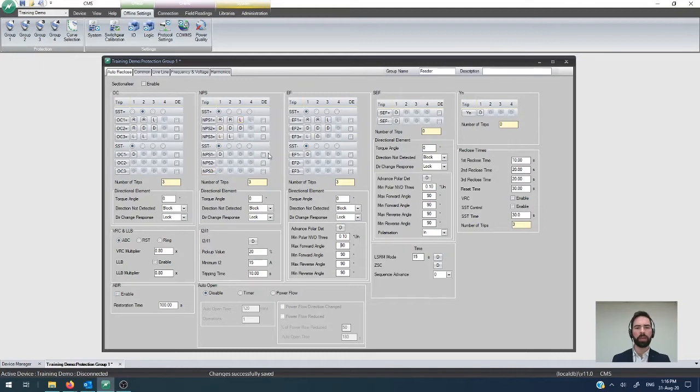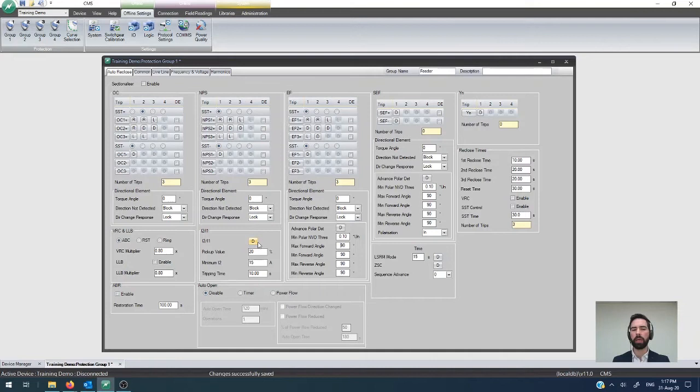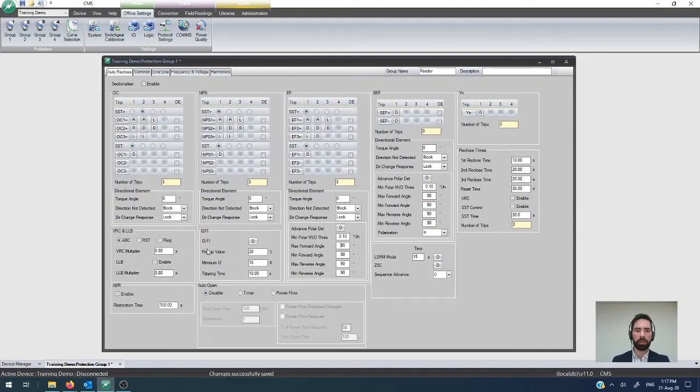Just to explain what the background is in the application of those features, there is a lot of value in implementing this stuff. In particular, the i2 on i1 configuration tends to be quite simple and works fairly well across most networks. If it's not something that you're using right now and you want to have the ability to detect broken conductors, something that will not be picked up by overcurrent or earth fault, then I strongly encourage you to check that out and consider rolling it out within your network.